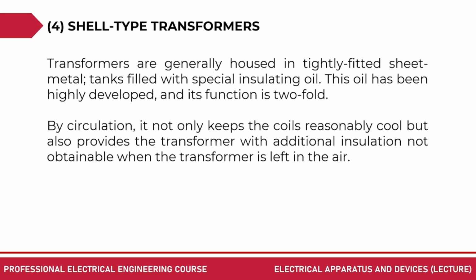Transformers are generally housed in tightly fitted sheet metal tanks filled with special insulating oil. This oil has been highly developed and its function is twofold. First, by circulation, it keeps the coils reasonably cool, and second, it also provides the transformer with additional insulation, not obtainable when the transformer is left in the air. We need oil because we know that when current flows through the coil, there will be heating. And to cool it, we have the air or oil. Okay, we'll talk about it in a while.